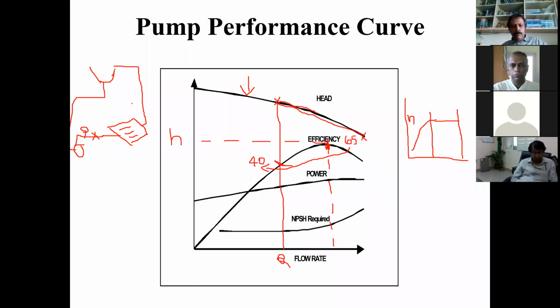The funny part about the pump is we don't know where we are losing the power. If you go to the industry, the process people say it is an efficient pump. What is an efficient pump? For them, as long as the pump delivers the required quantity of water at a particular head, it is an efficient pump. Nobody knows what is the efficiency of the pump, at what efficiency it is operating. Whether it is 65% or 40% or 30%, nobody knows. Because the pump is anyway meeting the requirements of the process. So nobody is concerned.